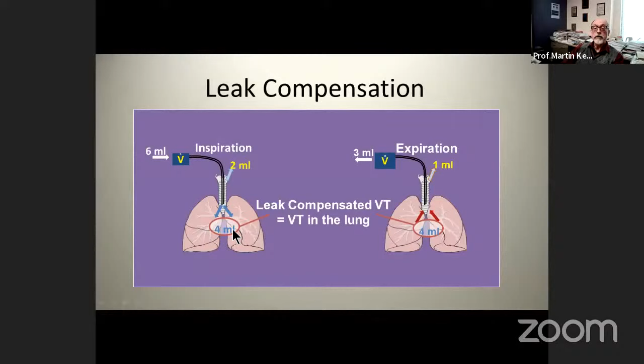And 3 ml. All right, so if we're targeting 4 ml and we're going by the exhaled tidal volume, the ventilator will increase the inflation pressure to try to make this number be 4. And in order to do that, it will actually ventilate the patient's lungs with a tidal volume a little more than 5 ml per kilo. So this could be a problem. And this is why if you have a large enough leak with volume targeted ventilation, it becomes a problem, except if you have the Drager VN500 and now the newer versions, 800 and 600, have this leak compensation phenomenon, which actually calculates the tidal volume based on the inspiratory and expiratory tidal volume measurement, and can use that calculated value of 4 ml to regulate our inflation pressure.